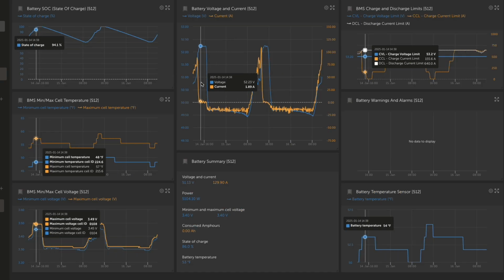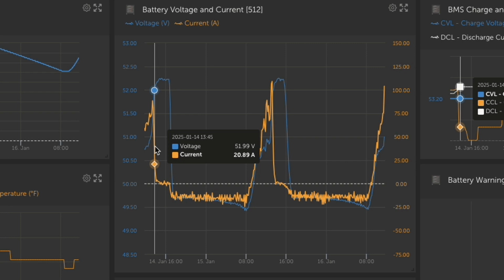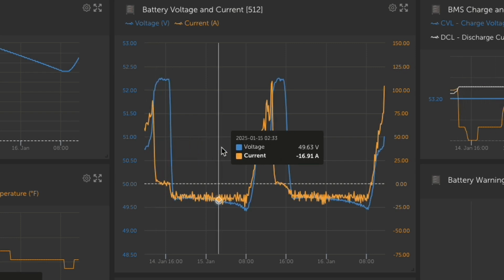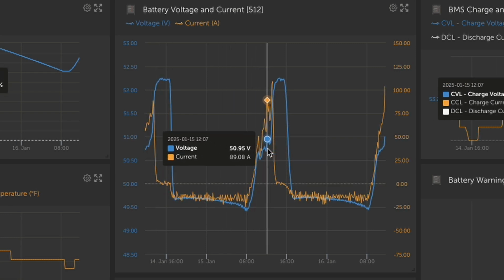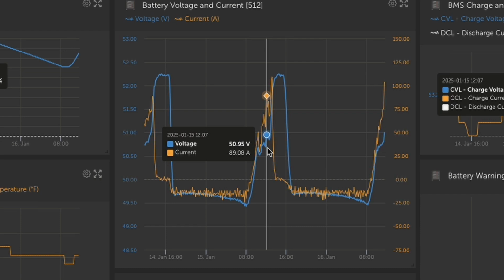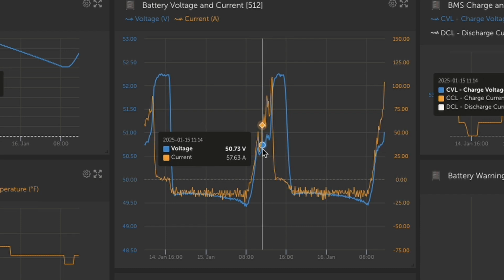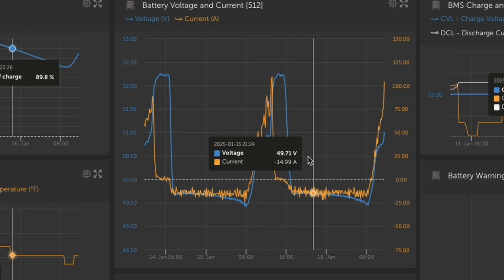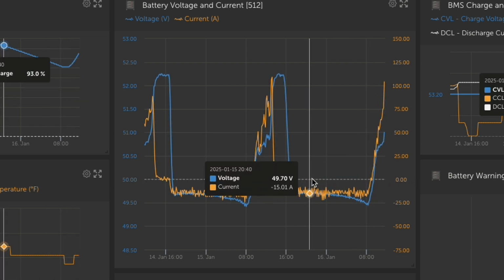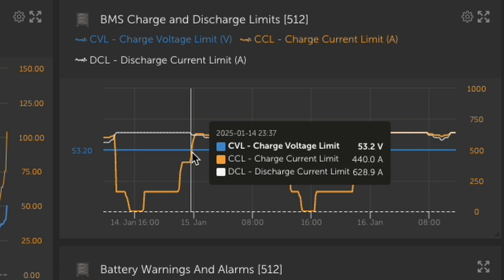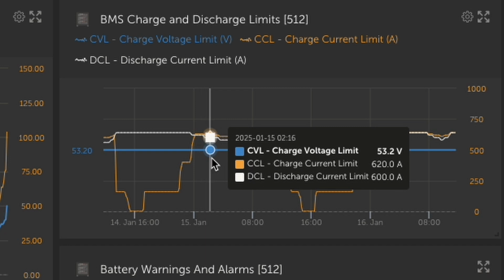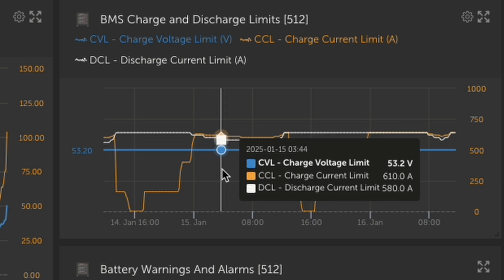Battery voltage and current. This is the voltage and current that's going into and/or out of the battery. You'll see here during the day, this charge current is positive. It's charging, adding to it. Overnight, it is discharging, meaning it is below zero on this point here. This is the BMS charge and discharge current limits. These are what we were looking at on that page within the remote console.